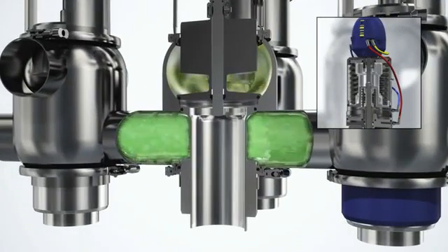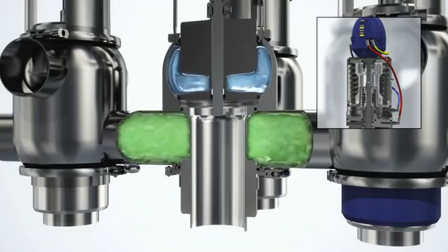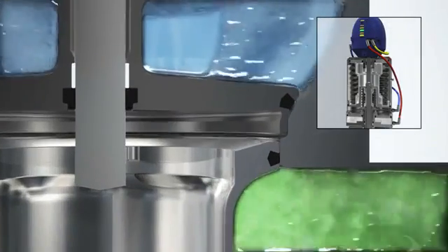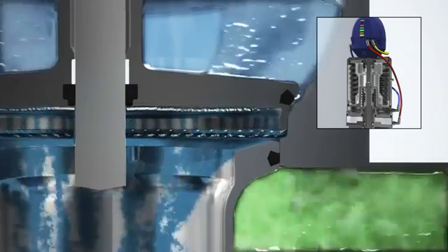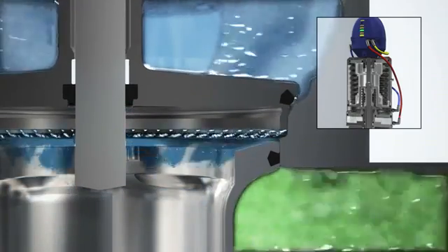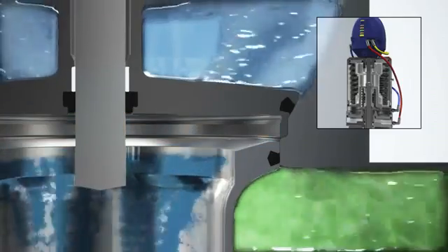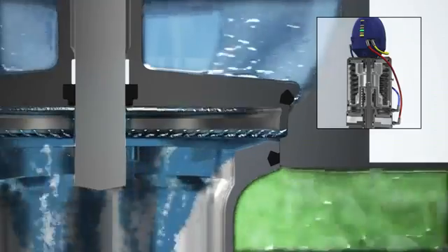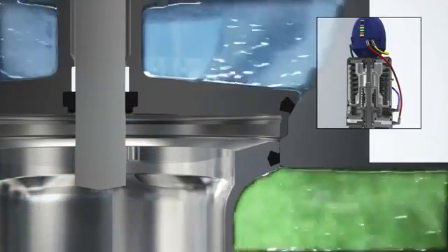It is completely safe to clean the upper valve body and plug seal while product flows through the lower section of the valve body. When cleaning the upper plug seal, the fast acting seat lift always creates a throttling edge due to the defined metal to metal stop in the actuator. This speeds the cleaning process by creating high turbulence and scrubbing effects, thereby minimizing CIP fluid consumption.